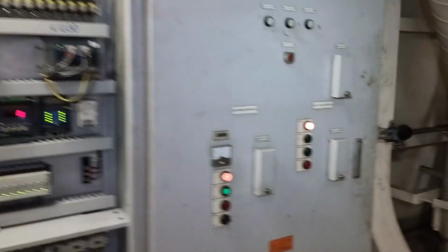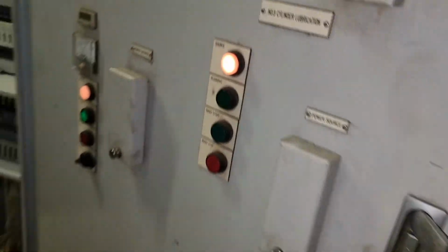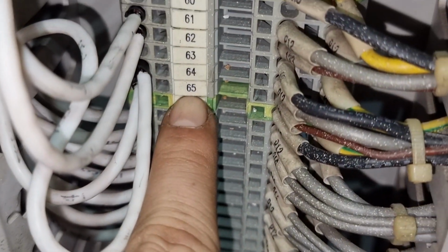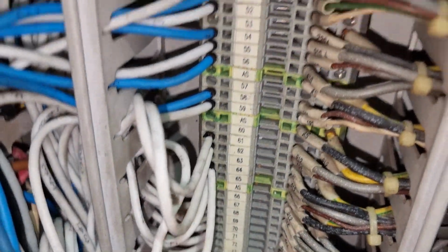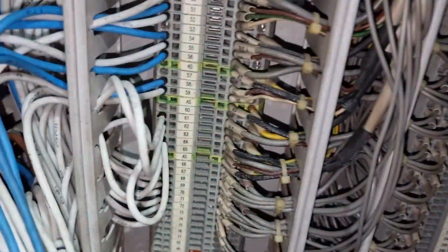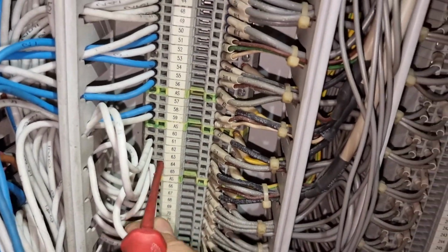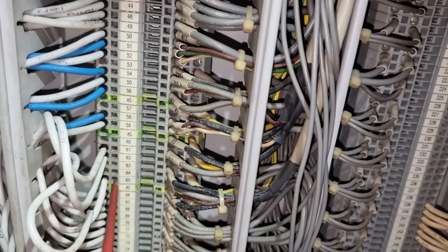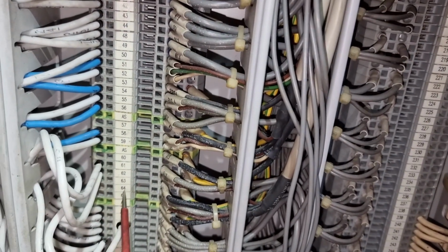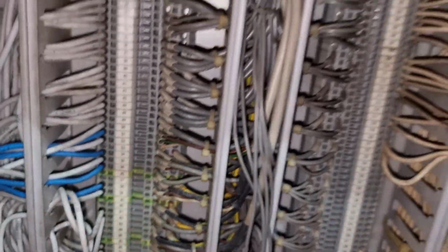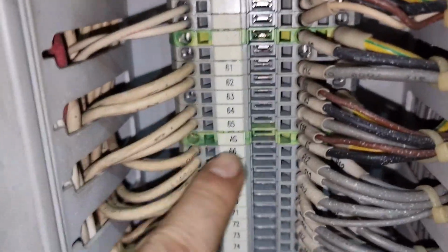Since everything is correctly wired, I'm assuming that there might be a problem in the new sensor installed. So I am thinking of doing a different approach, which will make my job easier. I will use the lube oil inlet pressure sensor of the number 3 generator and connect it directly to numbers 64 and 65 of generator number 4. Since the number 3 lube oil inlet pressure transmitter is in good condition, it should give a reading into our number 4 generator control panel.